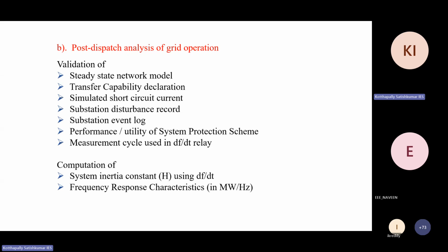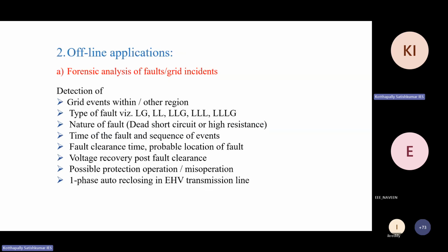You can also compare with PMU data, and compare your substation event log with PMU data, to check whether the substation equipment and instruments are working and giving accurate data. We can also discuss computation of system inertia H using df by dt, and frequency response characteristics. These are all benefits from PMU.